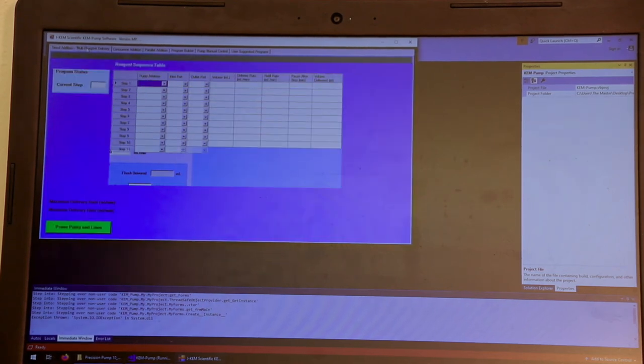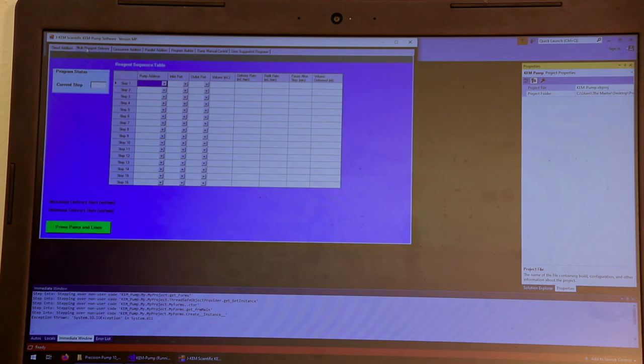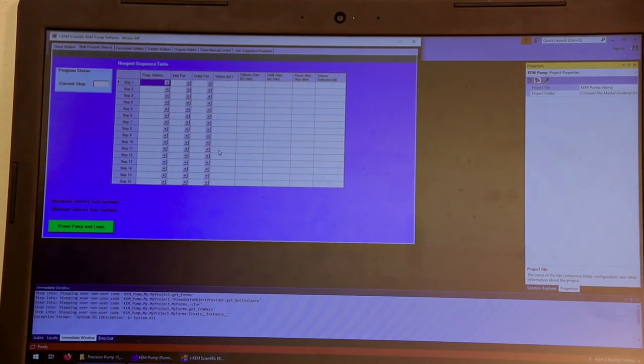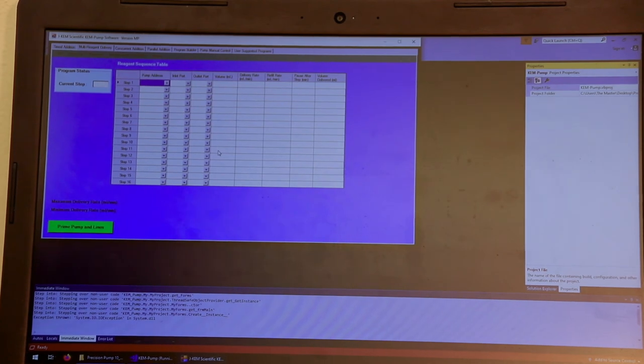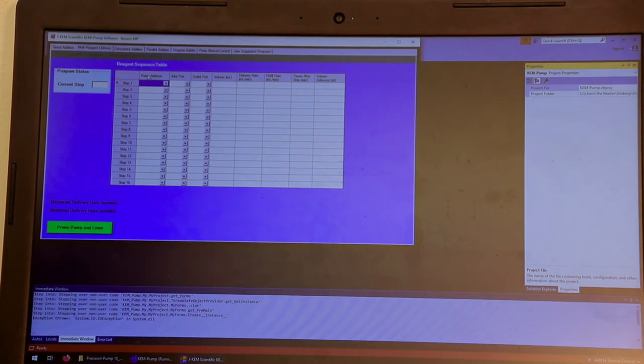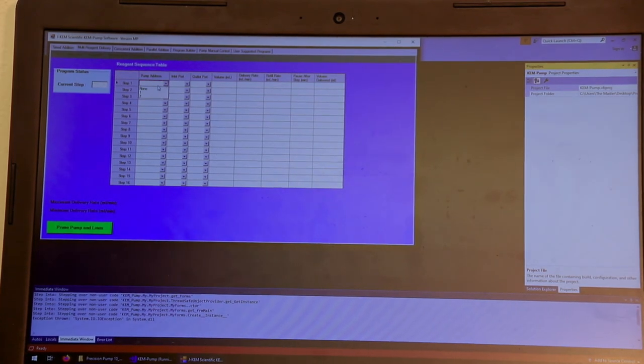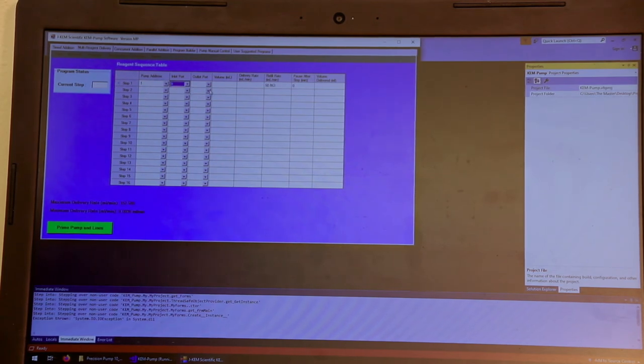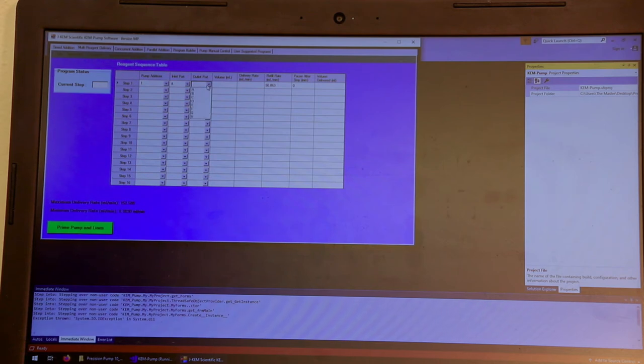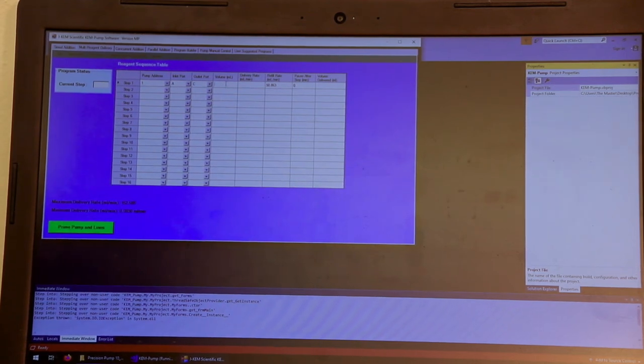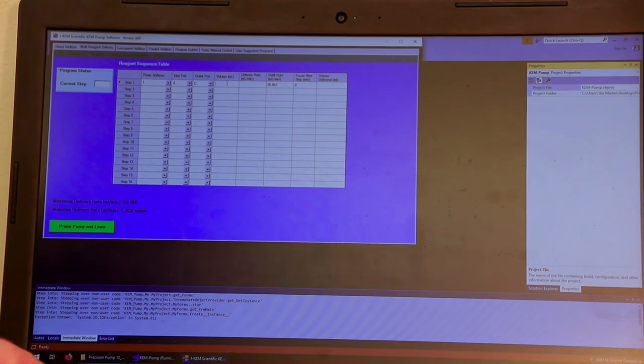The second one is called a multi-reagent addition. And in this one, you have an Excel-like table where you can actually create a program. So I can say I want pump one to go to port A, and then fill, and then go to port C.